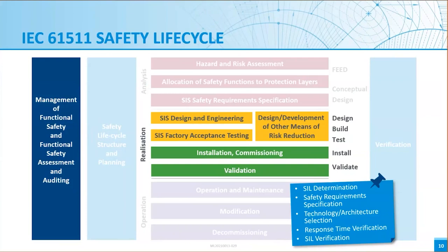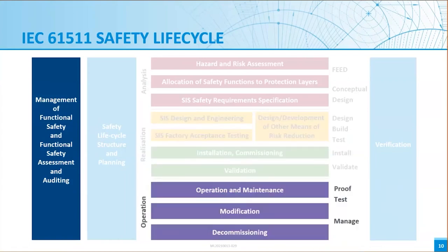The fourth bit, which is the topic of the talk today, is calculation of so-called process safety time and the response time of the SIFs to confirm that they can act in a timely manner. And the fifth activity, as shown here, is to verify that the selected design of the SIFs meet their SIL levels. Once all these activities are finished, they go through a number of tests and commissioning activities at site before they go into the final operation phase, where it is required that the system is maintained and tested throughout the lifetime to ensure the reliability of the system is as per original requirements.